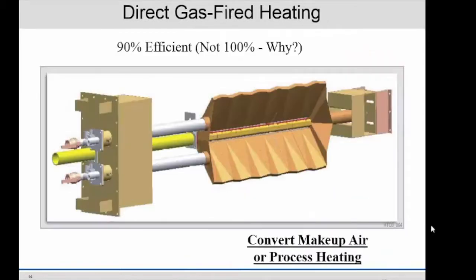Okay. Oh, direct gas fired. So you're going to have a lot of makeup air in these industrial facilities, and they've probably got steam coils. And those steam coils probably freeze every other year, and they're changing them out every other year. Get rid of the steam and go with direct gas fired. This happens to be a Maxon burner, which is a Honeywell product. We don't have to use that, but it happens to be Honeywell. And so if you're converting makeup air from steam or hot water to natural gas, direct gas fired.